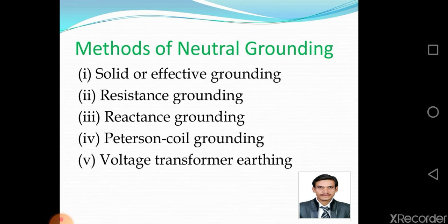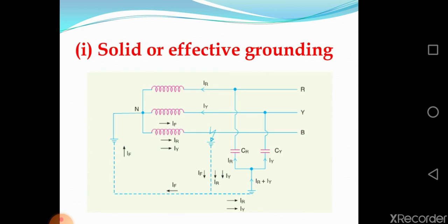Methods of neutral grounding: solid or effective grounding, resistance grounding, reactance grounding, Peterson coil grounding, voltage transformer earthing. Solid or effective grounding. You have seen this diagram. In this diagram, R, Y, B are the three lines, and the current flows across the line. IR is for the R line, IY is for the Y line.